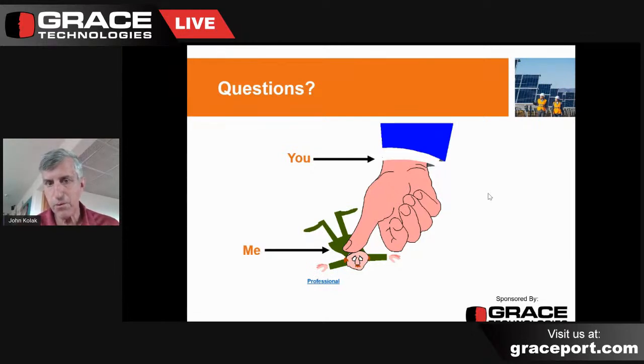Plan B would be to use, an unfortunate term, a chicken switch, which is a temporary device you can magnetically connect to the handle on a switch and actuate a breaker remotely, or using an insulated switch stick to add distance between you and the arcing energy. Any of those are possible solutions when you have more incident energy than you can handle. But the most common thing you're going to do is put additional distance between you and it.